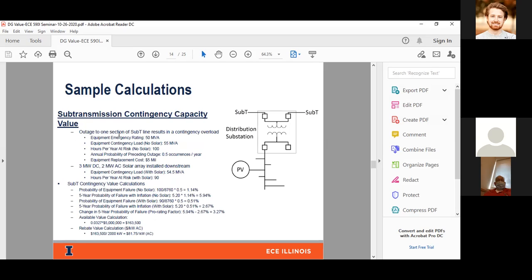This is a little bit more complex. It's the subtransmission piece. So on the higher level here, we consider some contingency scenarios where if you lose one line, there's a higher risk of you creating an outage, or there's higher risk of you really overloading that other line when you try to serve multiple loads. So we take into account these probabilities. And then we still continue to use the same proration factor. So we have a prorating factor of the change in probability of creating a violation on that subtransmission line.